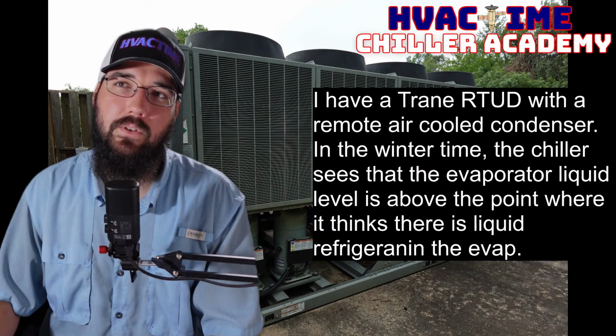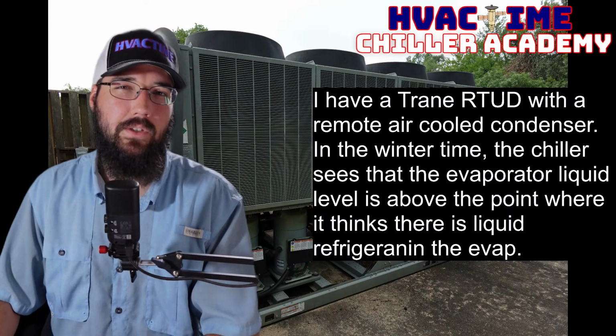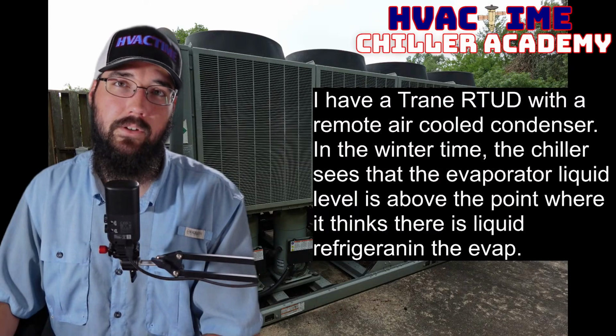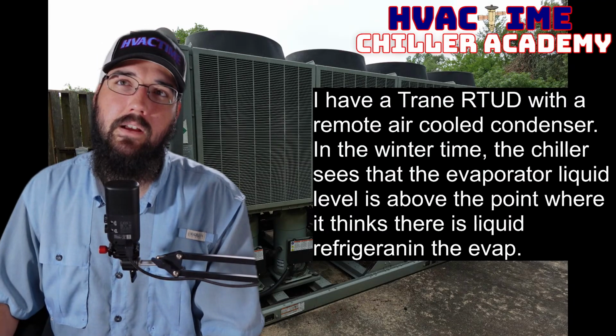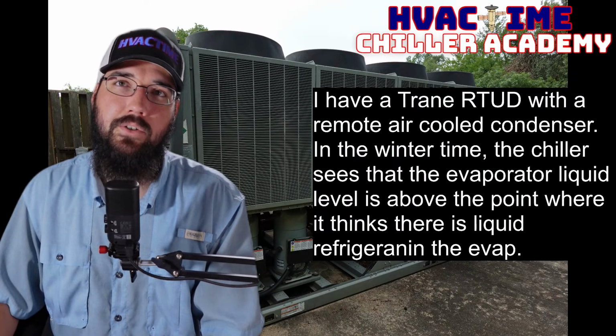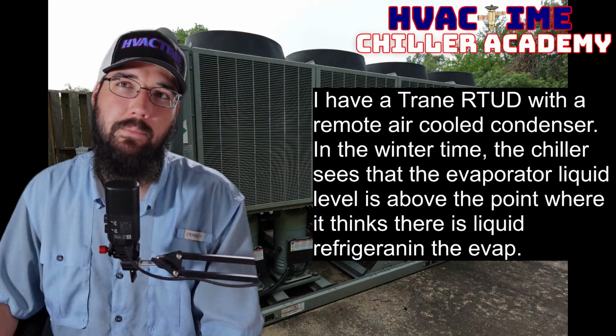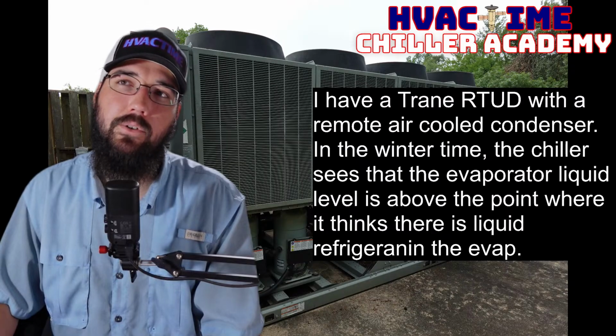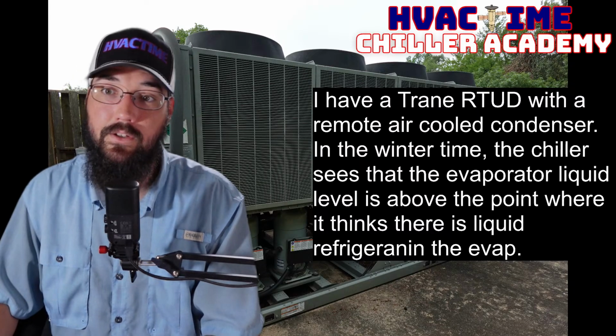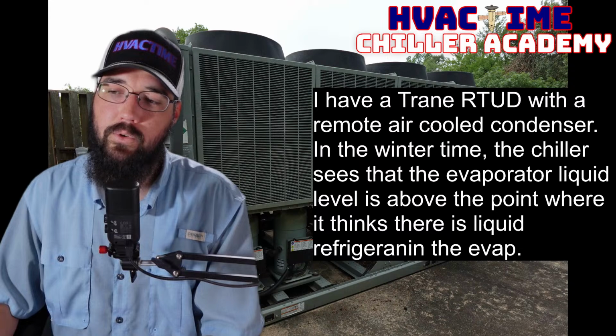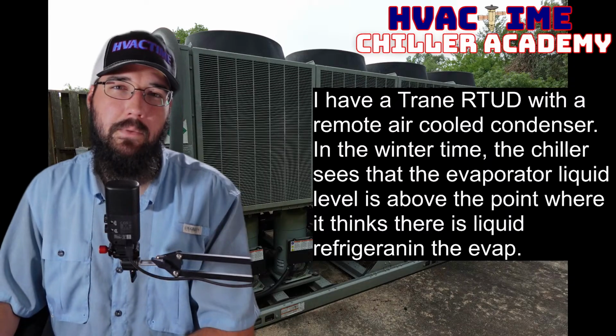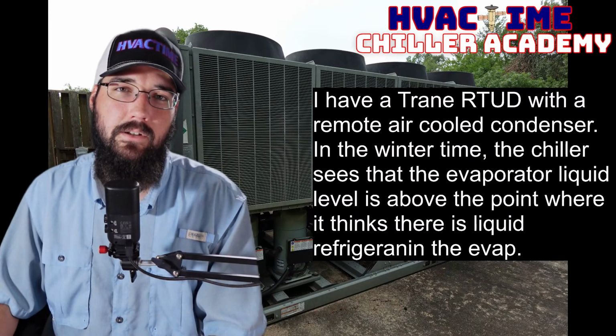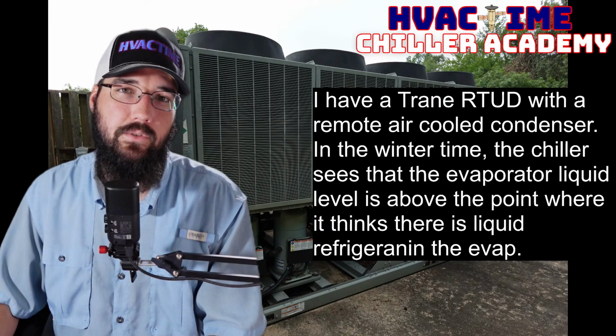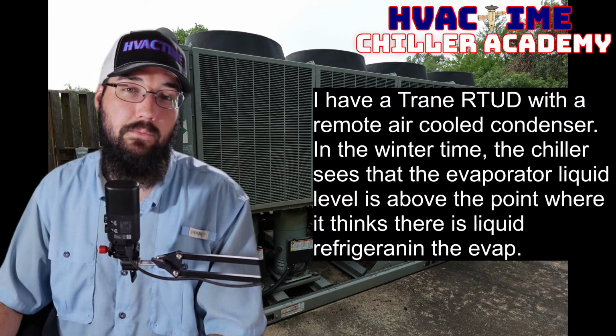I'm trying to think though, because I don't remember. I know with a CVH, you can push those to about 70 degrees before that eductor starts having problems on the condenser saturation. I wonder if the RTHD, especially with a remote condenser, because you're also going to have some pressure drop and stuff too to factor in. I wonder if those, or I said RTUD, sorry. I wonder if they need maybe a slightly higher condenser saturation. Maybe 70 degrees may be too much for those. So maybe running closer to 80 would be better.